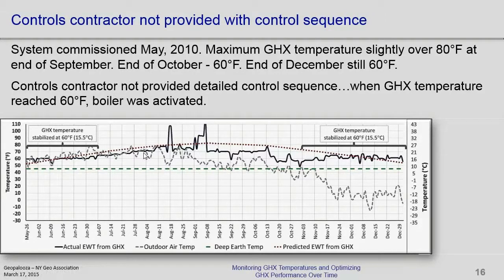So they assumed that because there was a gas boiler and they wanted the gas boiler to come on at 60 degrees, like you would with a normal boiler cooling tower system, heat pump, as soon as the ground loop hits 60 degrees, you want the boiler on. So what happened is the system worked fine in heating. The system in the first year worked fine in cooling. And if we had caught this earlier, we'd have seen that it started out at 60 degrees. It should have caught that right there, instead of by the time we got over here.